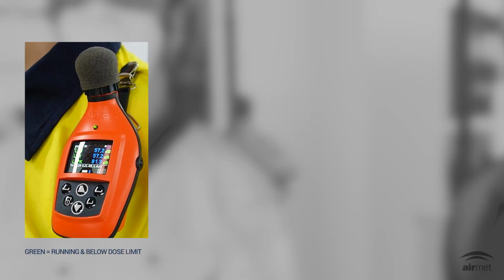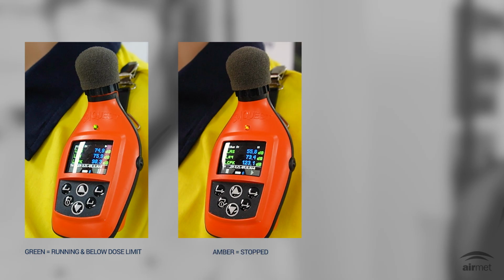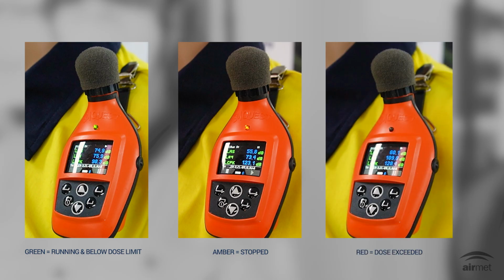Whilst wearing the device, you can check the LED status indicators. A green light indicates the unit is running and below the dose limit. An amber light indicates the unit has stopped recording. And a red light indicates that the dose has been exceeded.